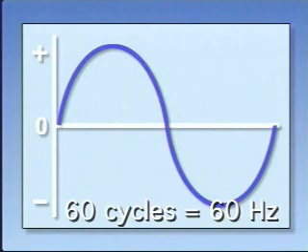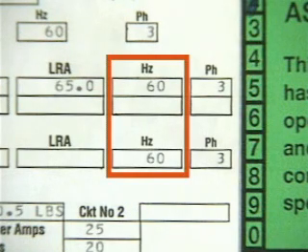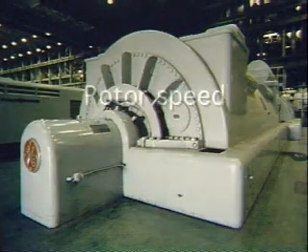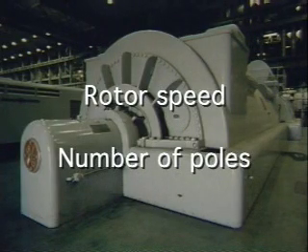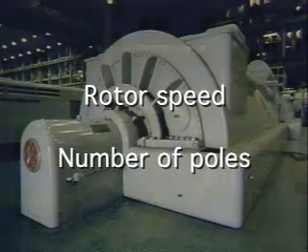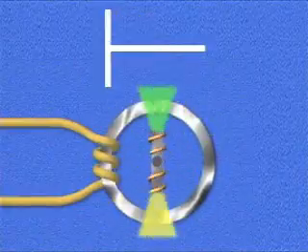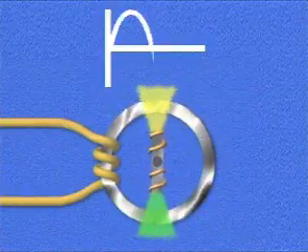It's important for a generator's speed to be consistent. Equipment that uses or produces electricity is usually designed to operate at a specific frequency. If the frequency changes, the equipment can be damaged. There are two factors that control the frequency of the current that is being generated: one is the speed at which the rotor turns, and the other factor is the number of magnetic poles in the rotor. In this illustration of a simplified generator, one cycle of current is produced for each revolution of the rotor, so the frequency equals the speed at which the rotor turns.